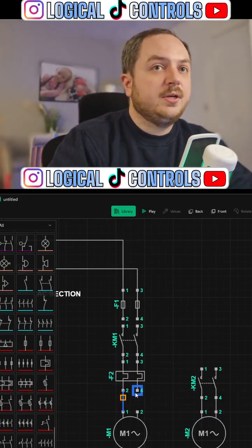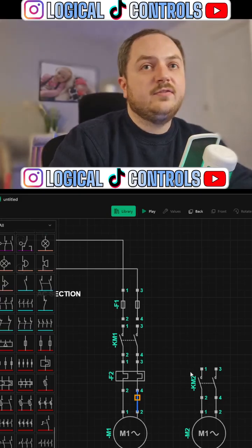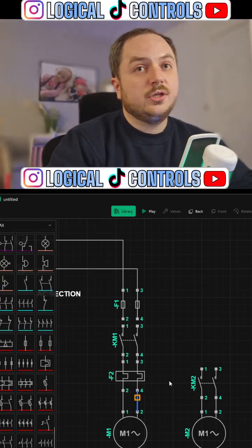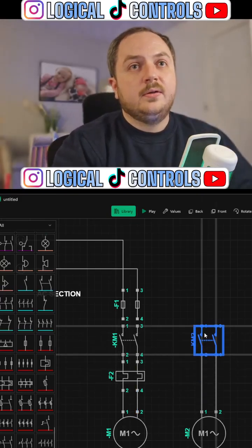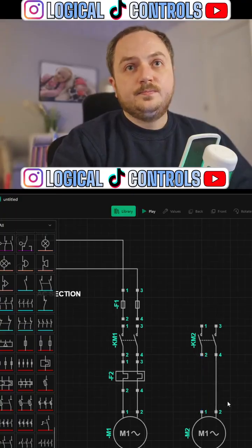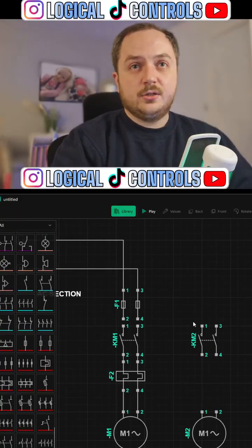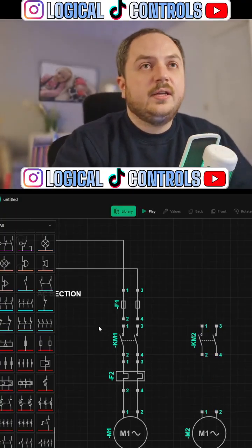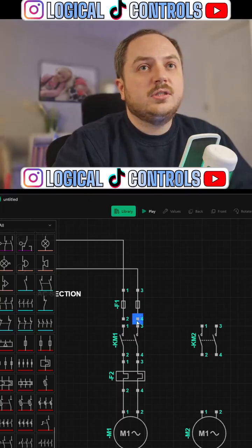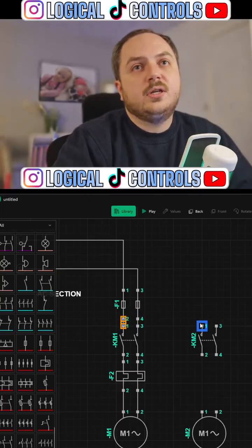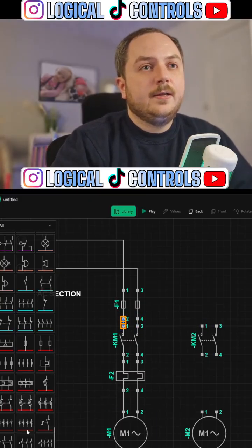Let's do it this way, just because I know I can get access to the F2 contact, which I can use in the control circuit to start the standby pump. That's what I'm doing now. Whereas I'm not entirely sure you can get access to a contact for the motor starter circuit breaker - the manual motor starter, is what I call it.